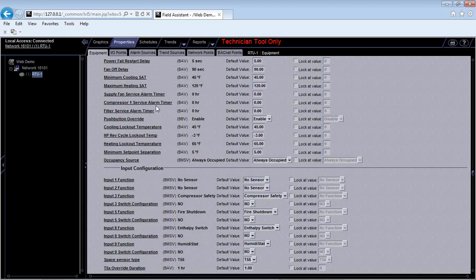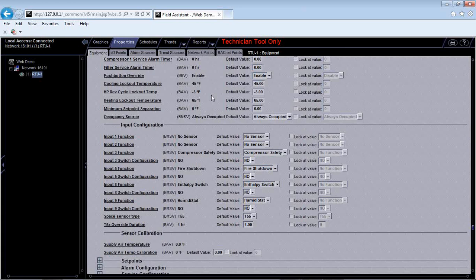So I usually try to set them at 0 unless I talk to the controls contractor about it and tell him, hey, this is going to go off every 600 hours. Do you want to set it for that? And he'll say yes. Okay. So I like to set those all at 0, one for compressor, one filter, one supply. If I keep scrolling down here, we have push button override.